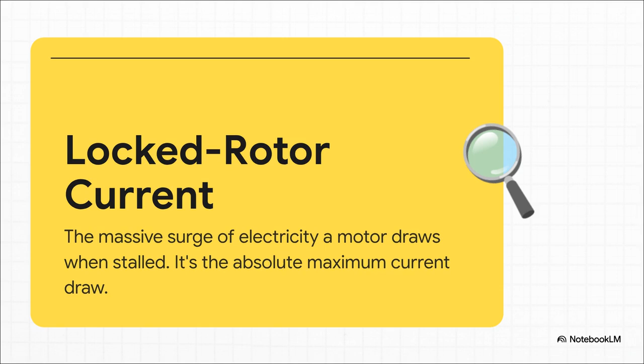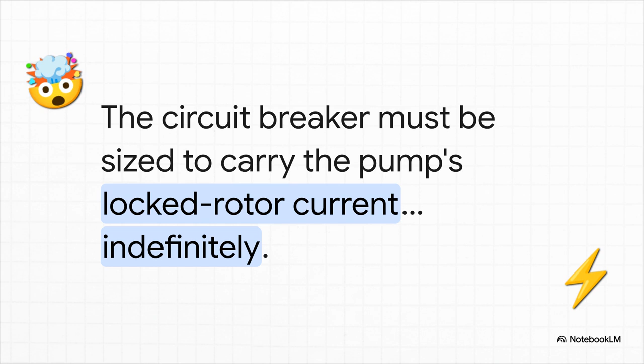So to really grasp how bonkers this is, you gotta understand this one term, locked rotor current. This is the absolute worst case scenario for a motor. It's the catastrophic surge of power it draws when the shaft is completely stuck or locked, but electricity is still being shoved into it. For a normal motor, this would last a fraction of a second before a breaker popped. And here's the rule that just breaks your brain. The circuit breaker isn't there to stop an overload. It is specifically sized to allow that locked rotor current, that self-destruct level of power, to flow through the circuit forever without tripping.